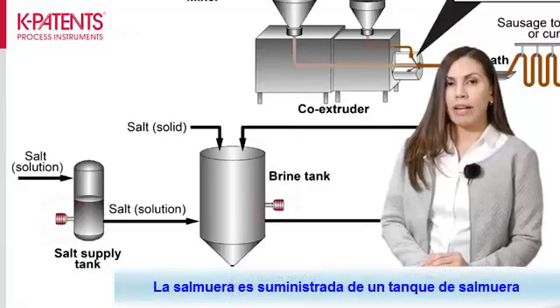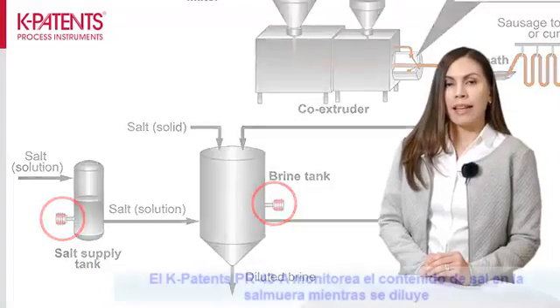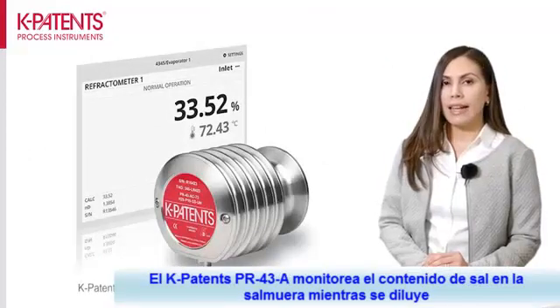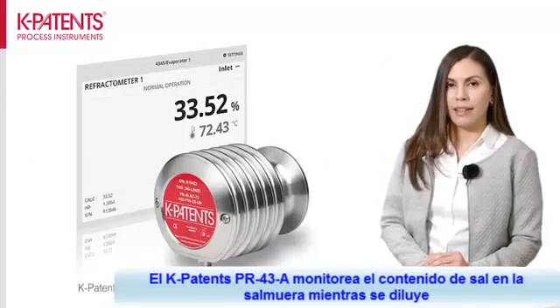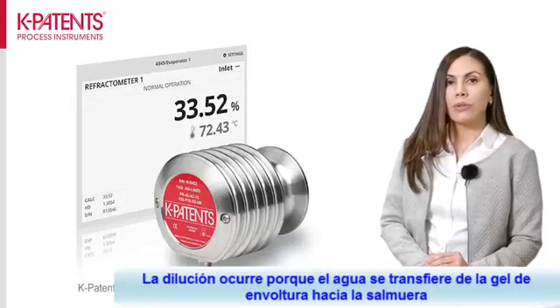The brine is supplied from the brine tank and the spent brine is recycled to this same tank. The K-Patents PR-43-A monitors the salt content in the brine as it gets diluted. Dilution happens because water transfers from the casing gel to the brine.